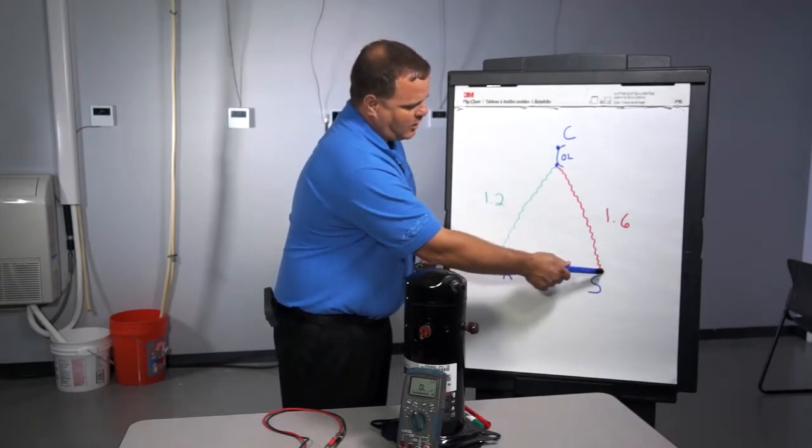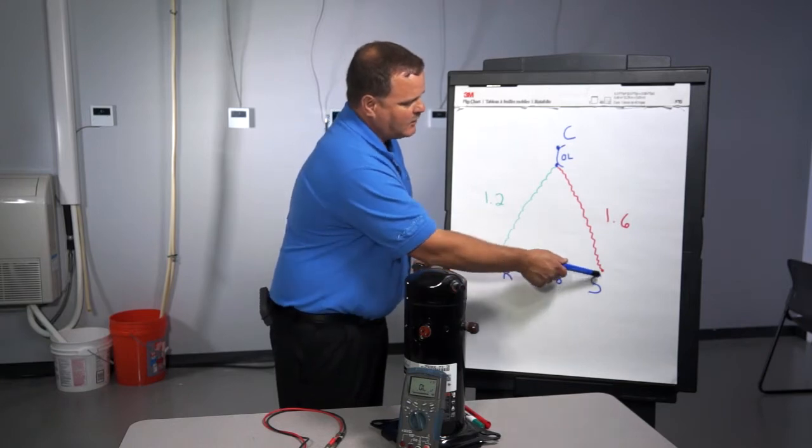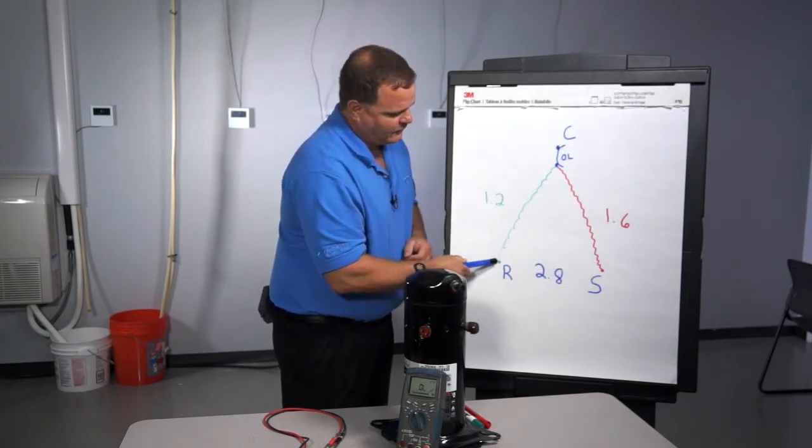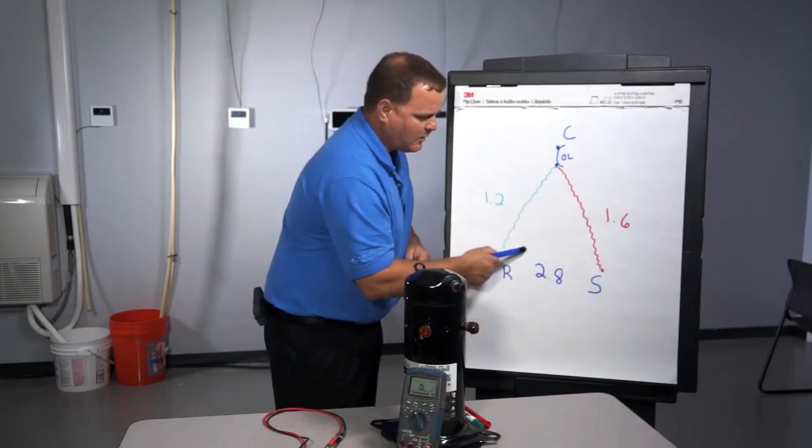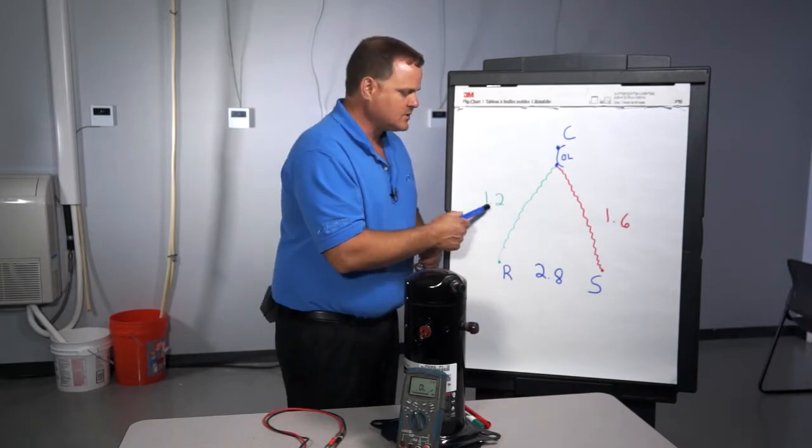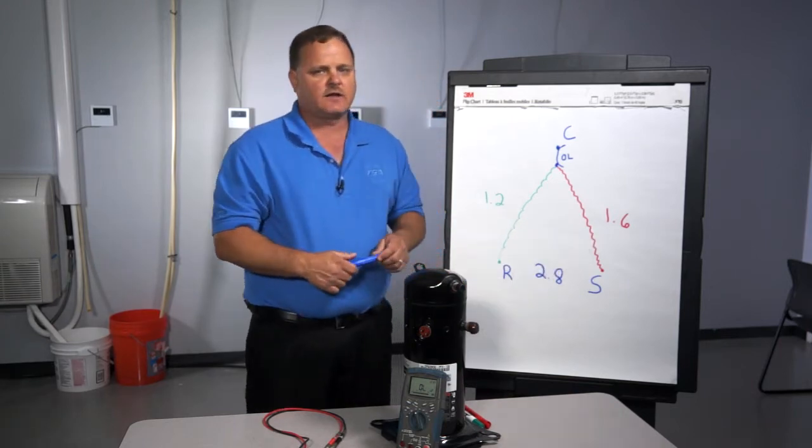And then if I measure from start to run with my meter leads, you can see I got an electrical path all the way through, and that's why you come up with 2.8 ohms, which is these two numbers added together.